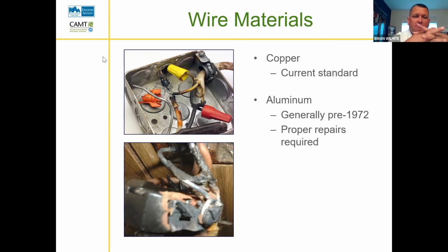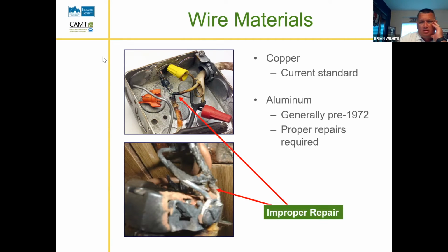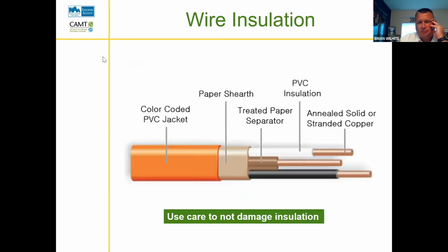It gets hot, melts the wire nut, which was not the proper wire nut for an aluminum to copper connection. They make specific lugged connections for these because you really need to make them better, and definitely need to hook up the ground. So both of those are improperly repaired. We look at Romex.